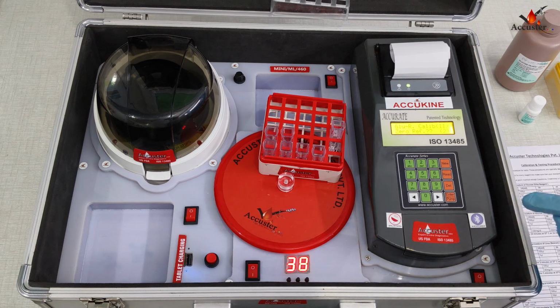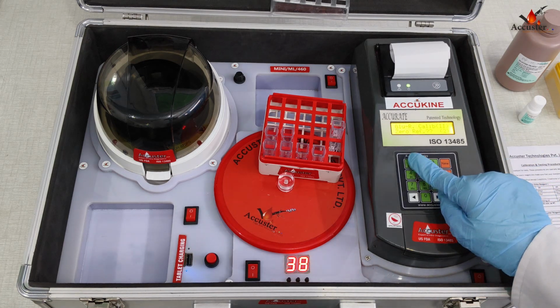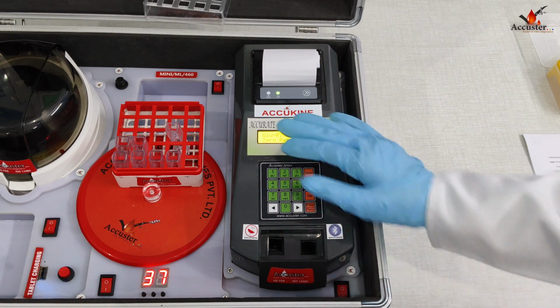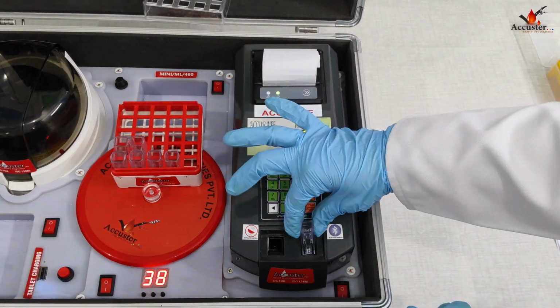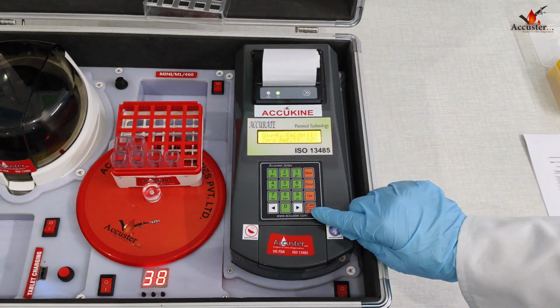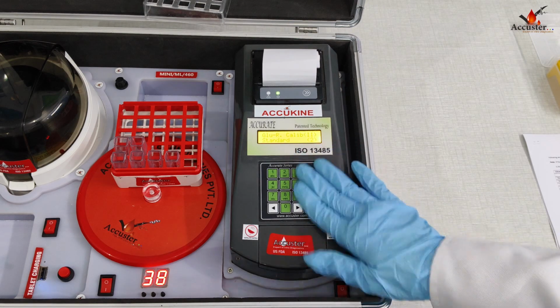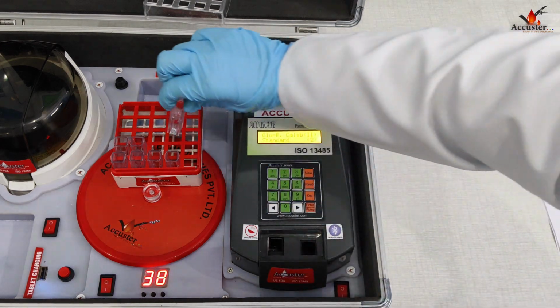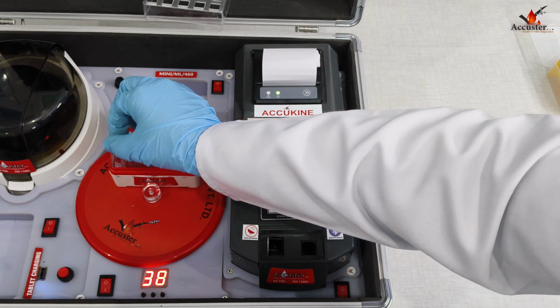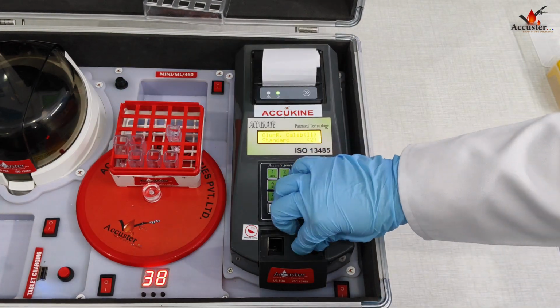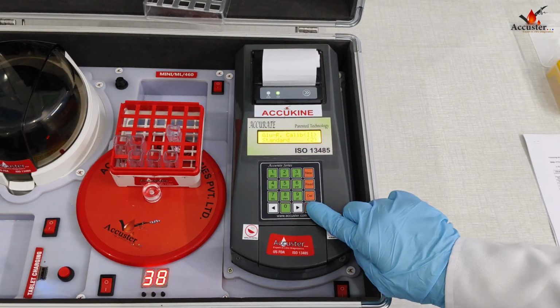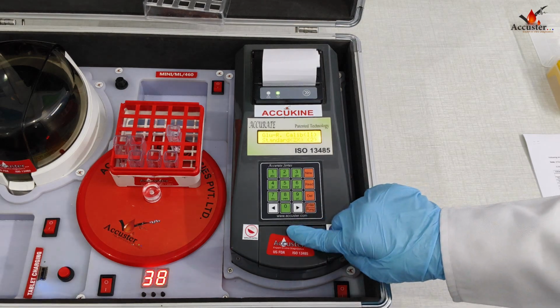The machine asks for 0 reference. To set 0 reference, we will place the cuvette with distilled water and press enter. Then machine asks for standard. And for that, 1x, insert cuvette labeled as 1x and then press enter.